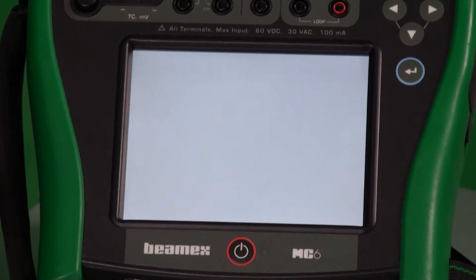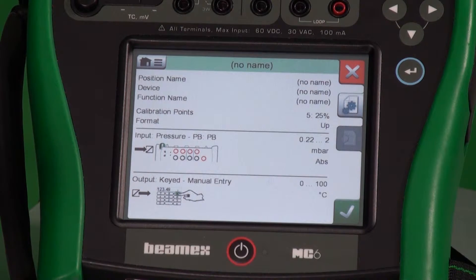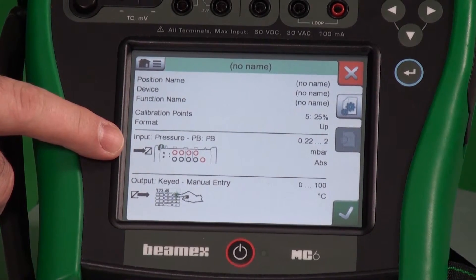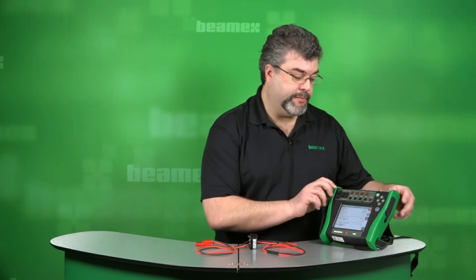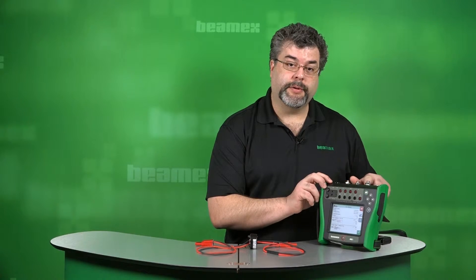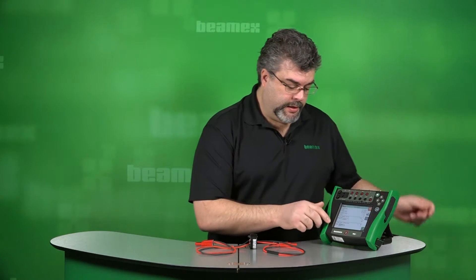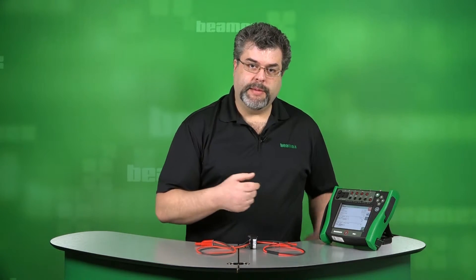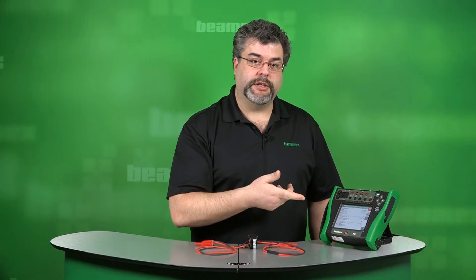Instead of switch, maybe you are calibrating a pressure indicator. So we still have pressure on the input. We can choose keyed as our output. That tells the technician that we're measuring pressure on the input and it tells what port to hook up to. We do have pressure ports across the top here, and we'll be keying in the values of the output.